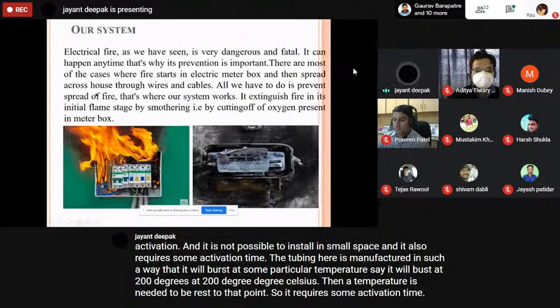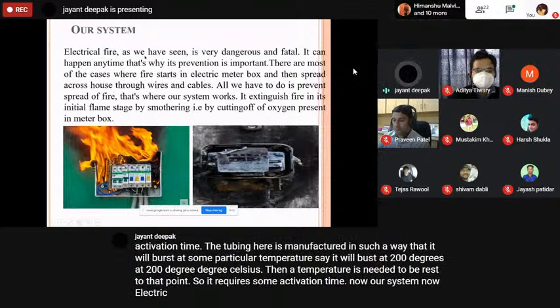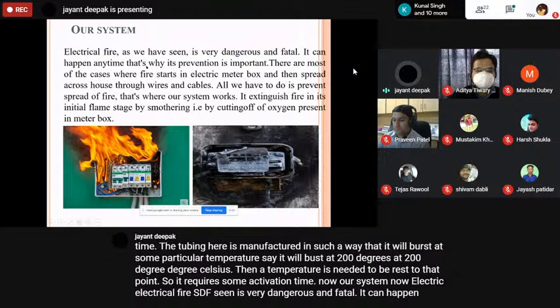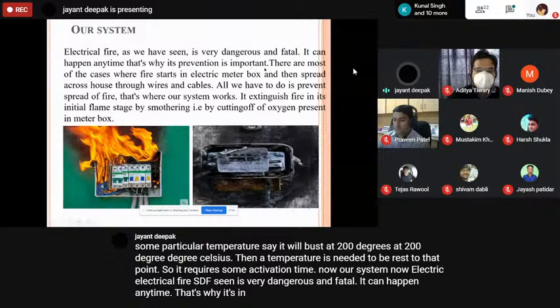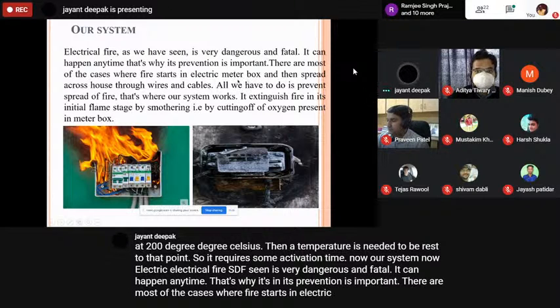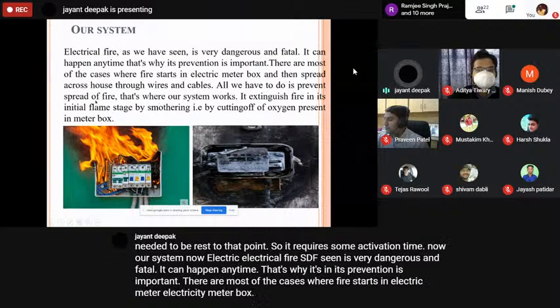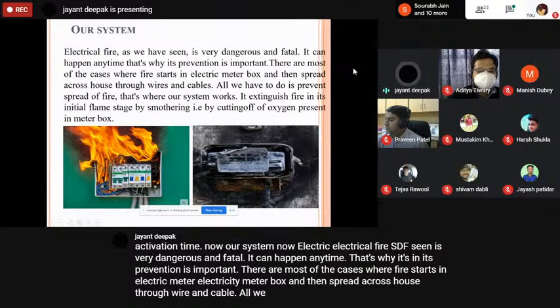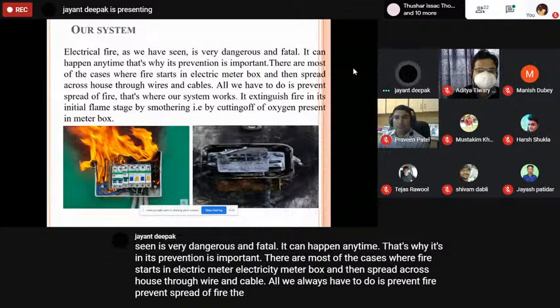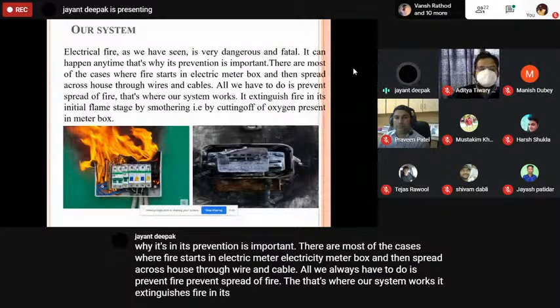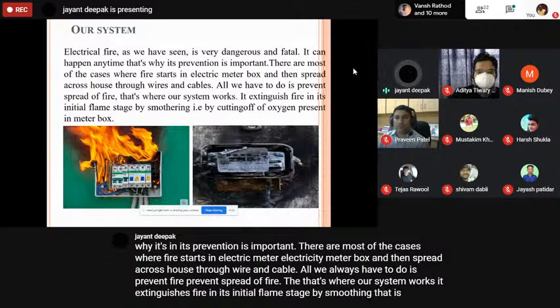Now our system. Electrical fire, as we have seen, is very dangerous and fatal. It can happen anytime, which is why its prevention is important. In most cases, fire starts in the electricity meter box and then spreads across the house through wires and cables. All we have to do is prevent the spread of fire. That's where our system works. It extinguishes fire in its initial flame stage by smothering, that is, cutting off the oxygen present in the meter box.